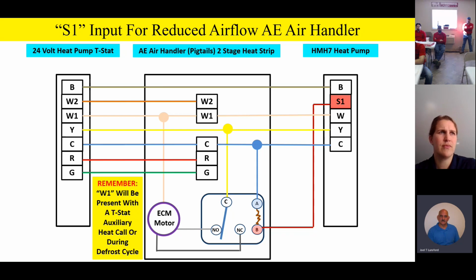In addition, you're going to have a W1 call or an auxiliary heat call during defrost cycle. So even if we were at reduced airflow and we go into defrost, what's going to happen? The outdoor unit's going to drive to 100% capacity, and it's going to drive the indoor airflow to the speed tap that we have for W1, typically on high. So here we are defrosting the unit now. The outdoor unit's in the air conditioning mode. We're defrosting the unit. You guys know how a heat pump works. And we're going to melt the ice off the outdoor unit, and we're going to energize the heat strip so we don't freeze the homeowner out during defrost.